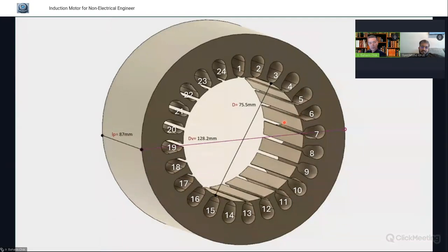So now we have a dire situation since we have not looked at the bearing issues, and it escalates into this. But given that once you put this together and the bearings are okay, it is unlikely that you can damage the stator core, unless there is a short circuit. Maybe because you run this motor with very low airflow, and then the motor becomes very hot, then the insulation inside the winding element that we saw just now gives way, and it touches the core, then it burns. So that can also be a possible cause without the bearing slamming into the stator core. If the bearing slams into the stator core, it is very severe damage. So nothing can be done.